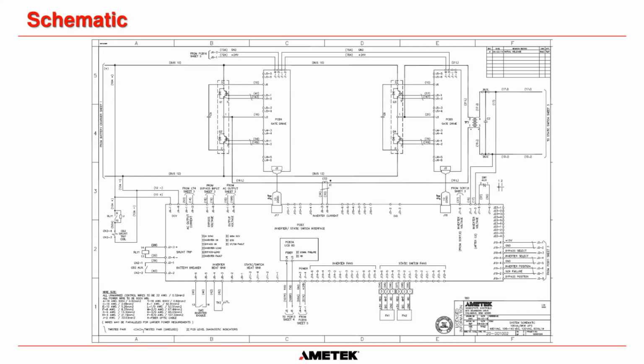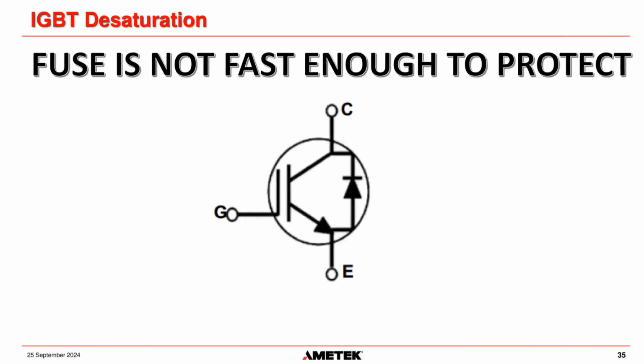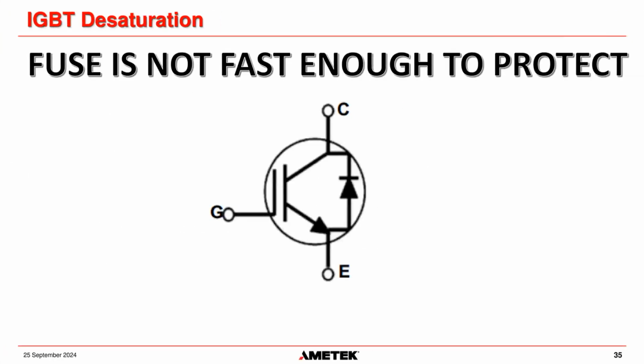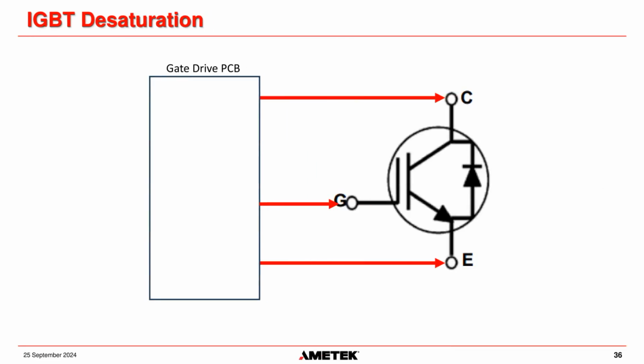So this is just actually what it looks like in our official drawings. And there's the primary of the transformer, there's the secondary of the transformer, and there's that capacitor filter circuit that I mentioned. And as I mentioned before, remember, a fuse is not fast enough to protect the IGBT. So what our control board has in the pulse width modulated system is a circuit that is called IGBT desaturation. It's a very, very big fancy name, and I'm going to try and explain this in the easiest way possible.